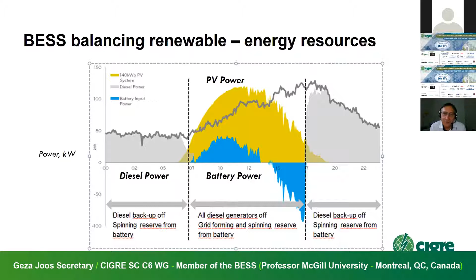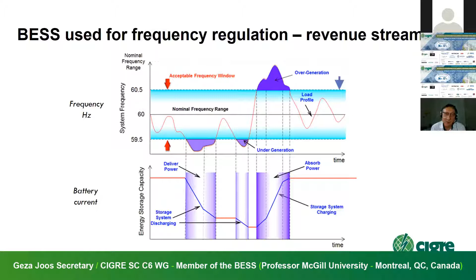This is another example of battery energy storage benefit, a revenue stream associated with frequency regulation. The battery energy storage essentially allows you to regulate the frequency within a band—here it's a 1 Hertz band—by providing energy when the frequency drops and absorbing energy when you have overgeneration. This revenue stream brings the most money in the US, and sometimes allows you to justify installing battery storage for other benefits, since frequency regulation is a short-term request from the system operator, so the rest of the time the battery can be put to other uses.